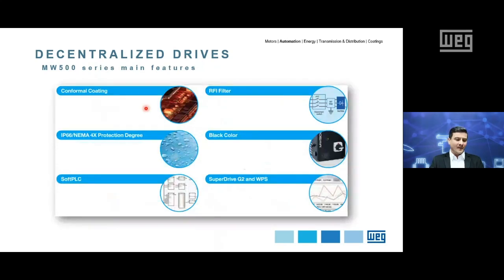These are some common features for MW500. Conformal coating board for class 3C2 as a standard, so this increases the lifetime of the VFD, protecting the electronic boards against corrosive atmosphere. IP66 enclosure suitable for indoor and outdoor application. Soft PLC function built-in that brings a PLC functionality to the VSD, allowing the user to customize application through the ladder program in this case.